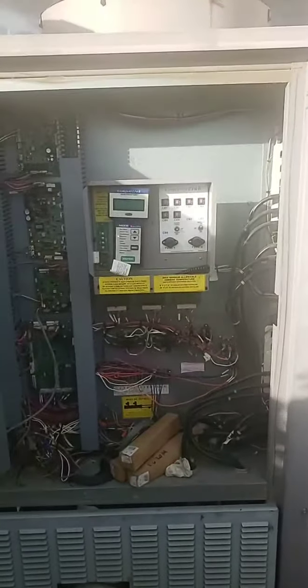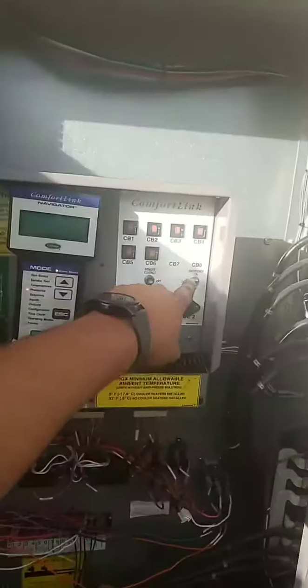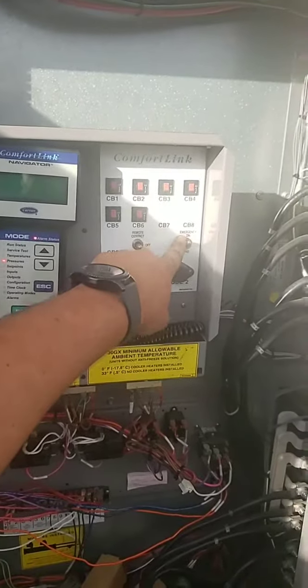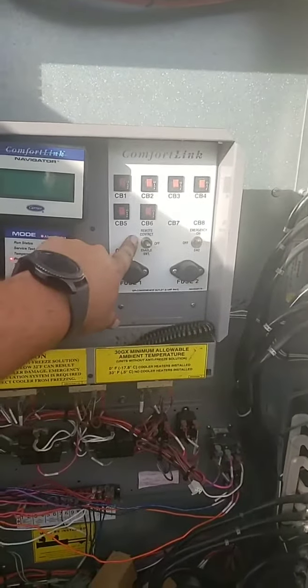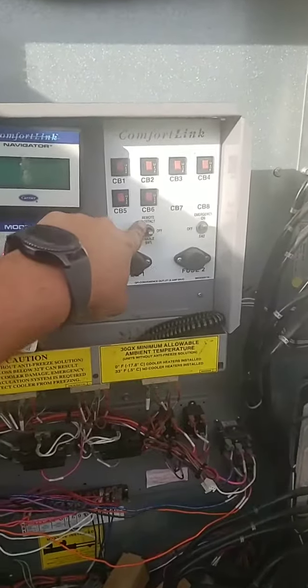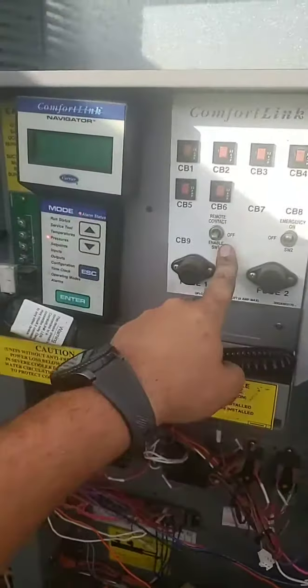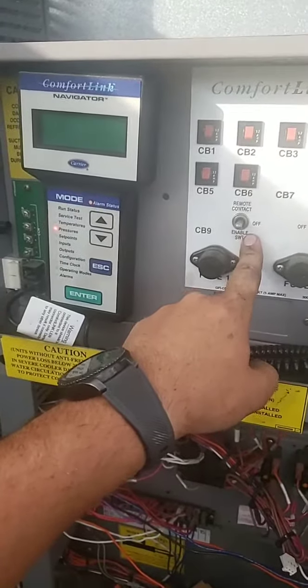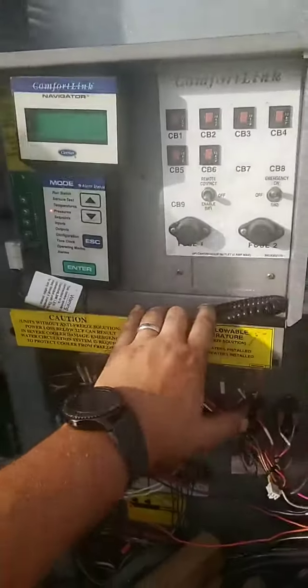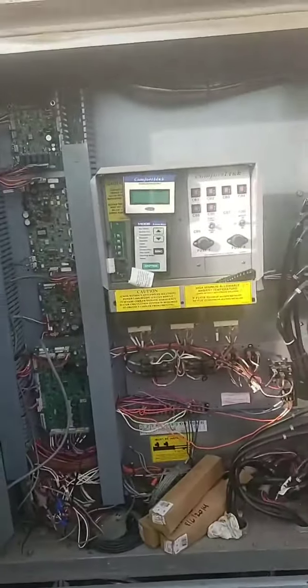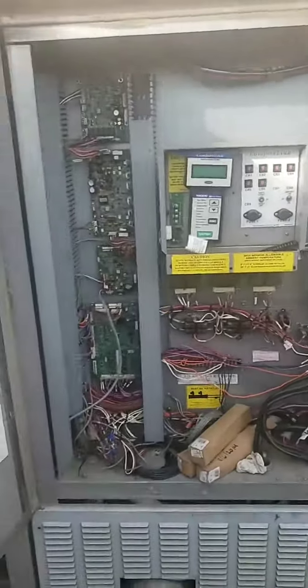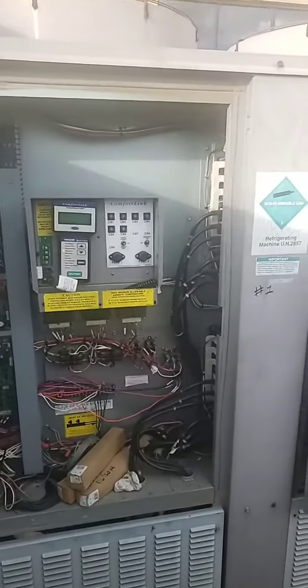Let's see. That's pretty well a basic overview, guys. You have an emergency on switch, just overrides EMS call. You can do remote contact, or if the EMS is not calling, then you can just strictly do an enable, and this will automatically bring it on as well. So yeah, guys, if you have any final questions, this is your Carrier 30GX 134 ton air cooled screw chiller.